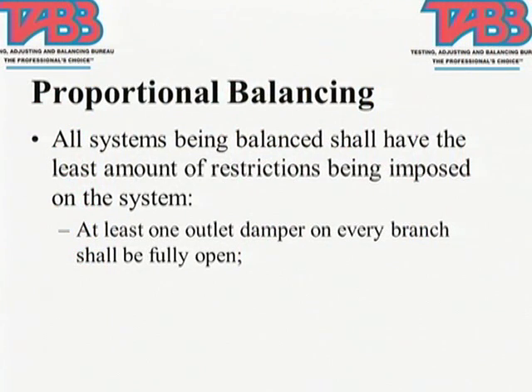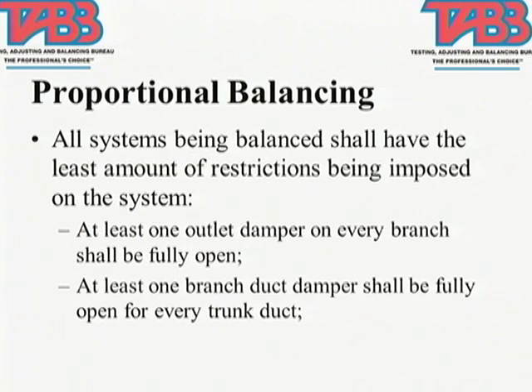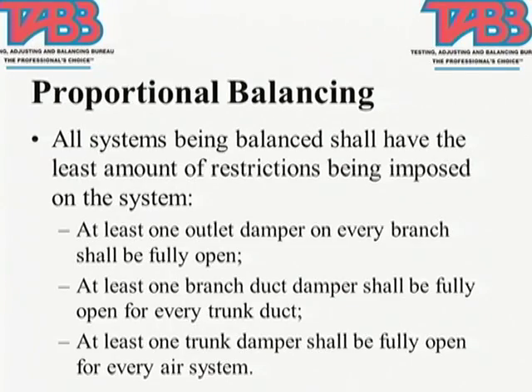At least 1 outlet damper on every branch damper shall be fully open is one of the rules. At least 1 branch duct damper shall be fully open for every trunk duct, and for every trunk, 1 damper needs to be open. Basically what it's saying is from your pump or your fan, you're going to be able to follow the fluid, whether it's hydronic fluid or air fluid, all the way to the terminal device, and there's not going to be any restriction on at least 1 of those. And that's what a commissioning agent should be asking for when they come out to commission a hydronic system or an air system. Instead of randomly grabbing 10% of the diffusers or 10% of the coils, they should be saying, show me where you have a loop that doesn't have any restriction and the damper is 100% open from the pump to the terminal device. Then you know you're putting the least amount of resistance on a system.